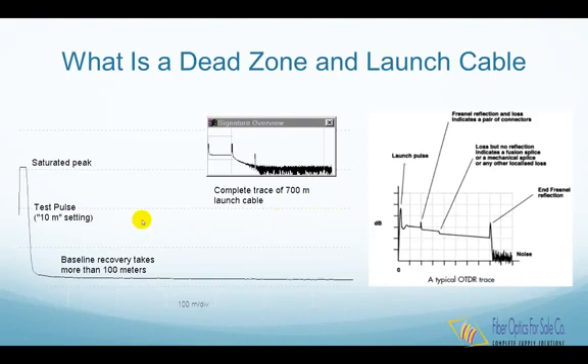The most common place you see this as a problem is caused by the connector on the OTDR itself. The reflection causes an overload, which can take the equivalent of 50 meters to 1 kilometer to fully recover, depending on the OTDR design, wavelength, and magnitude of the reflection. For this reason, most OTDR manuals suggest using a launch cable, which gives the OTDR time to recover before you start looking at the actual fiber under test.